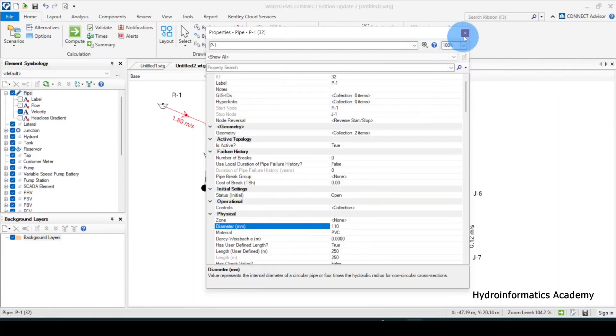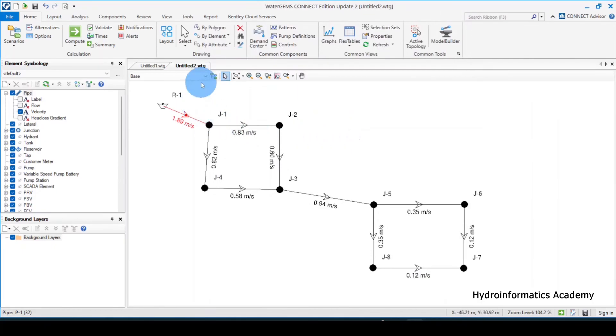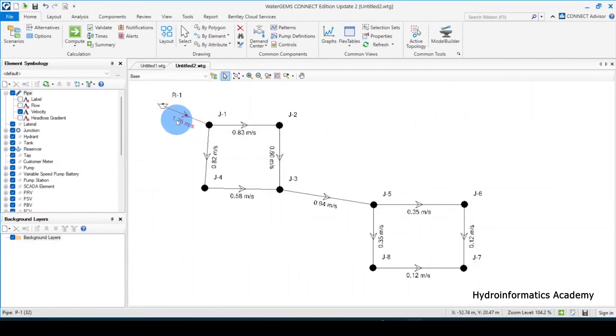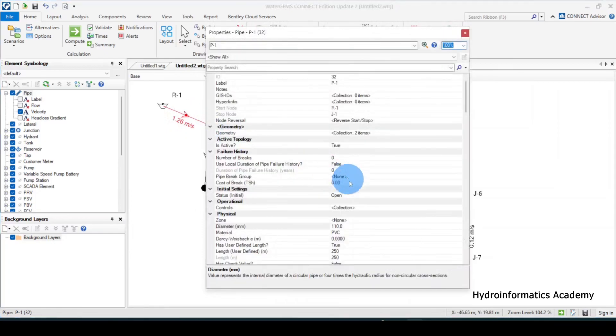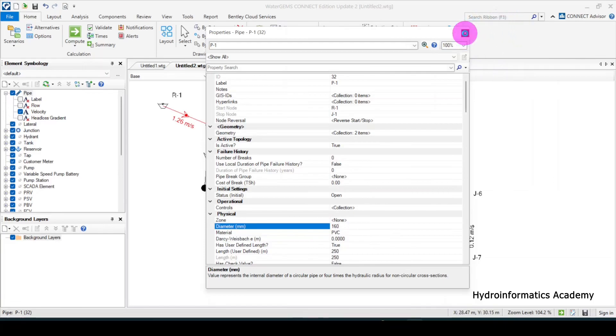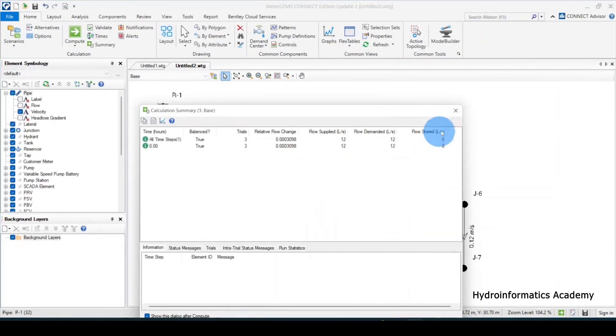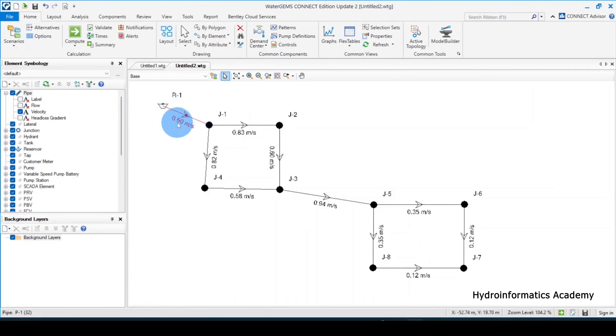From here I can just double-click the pipe. I'll increase the diameter to 110 — remember we are supposed to use the internal diameter, not the outside diameter. Let me click close and run the model again. You can see now we are having 1.26 instead of 1.89. Let me try 160 and see — now we are having 0.6. I'll maintain that.